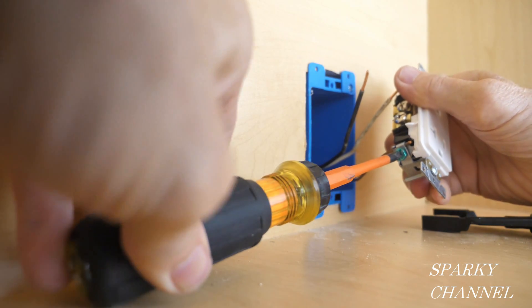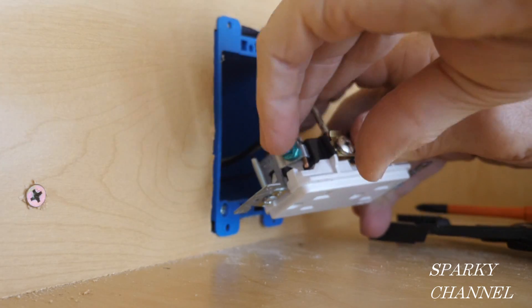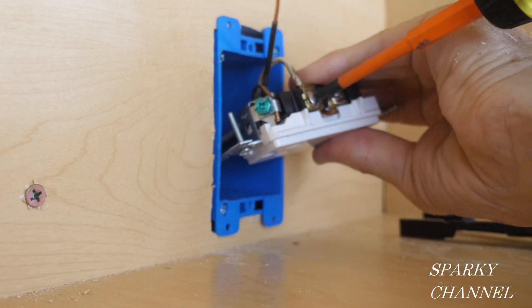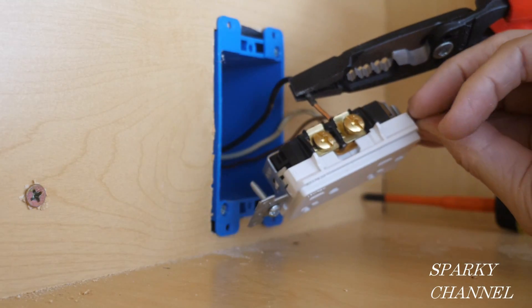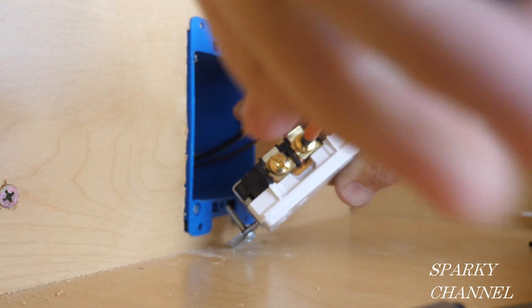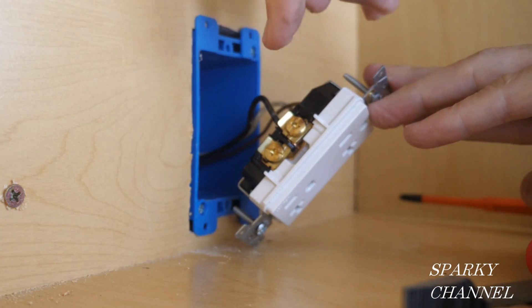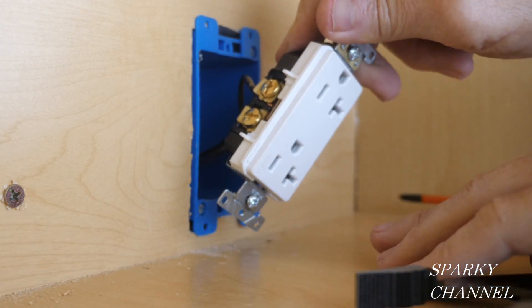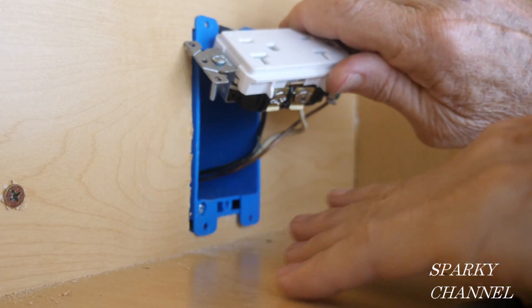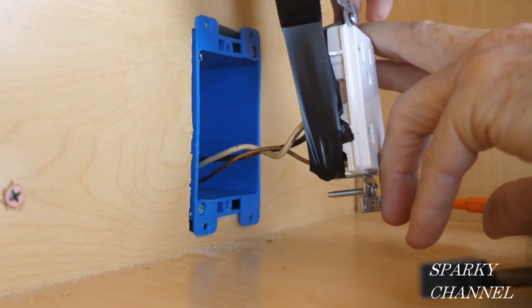I'm going to start by attaching the bare ground wire to the green grounding terminal of the receptacle. Next I'm going to attach the white neutral wire to the silver neutral terminal. That's very well attached. And next I'm going to attach the black hot wire to the brass terminal. So we have the black hot wire on the brass terminal, which is on the same side as the short slot for your plug, and the long slot with the T for the 20-amp receptacle is on the same side as the silver colored terminal. Now I'll put a few wraps of black electrician's tape around the terminals for safety.